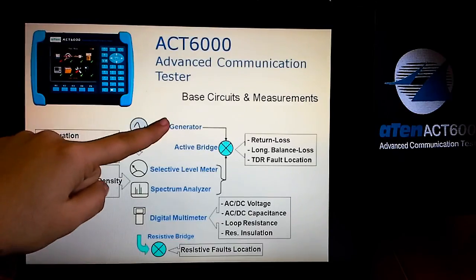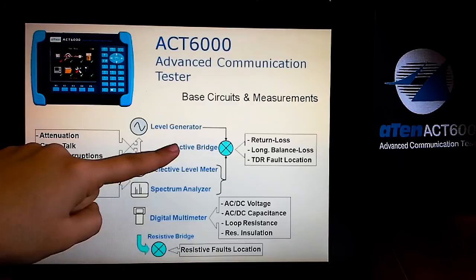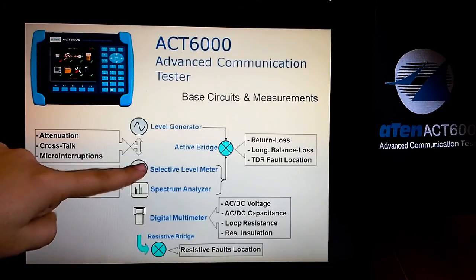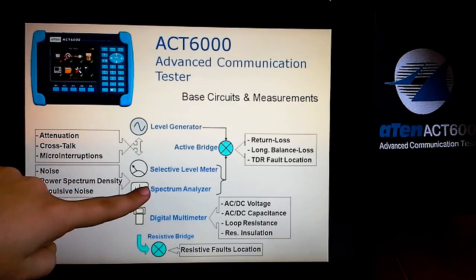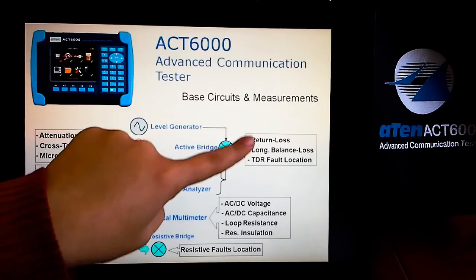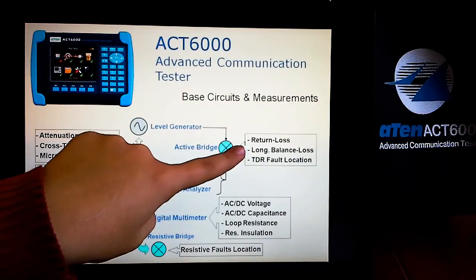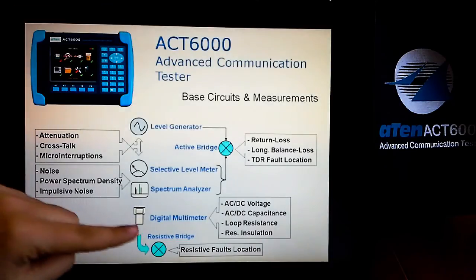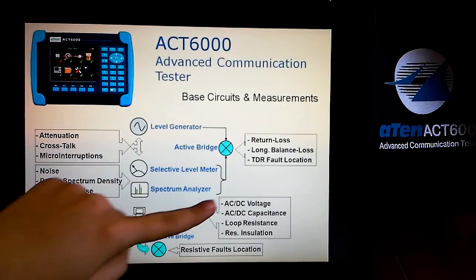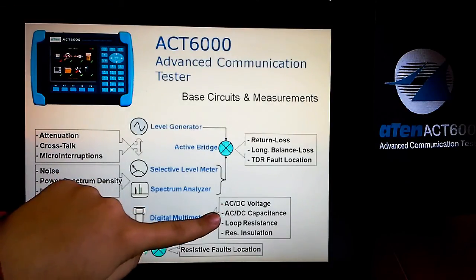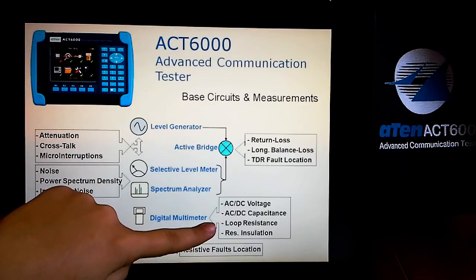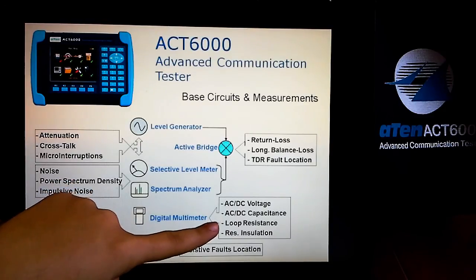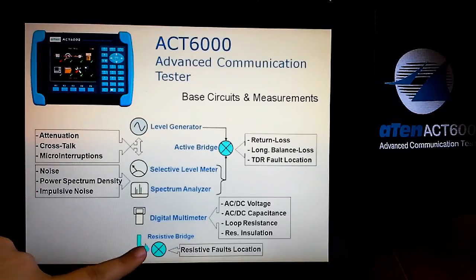From the level generator, active bridge, selective level meter, and spectrum analyzer, you can check return loss, longitudinal balance loss, and TDR fault location. From the digital multimeter, you can check AC/DC voltage, AC/DC capacitance, loop resistance, and resistance insulation. From the resistive bridge, you can check resistive fault locations.